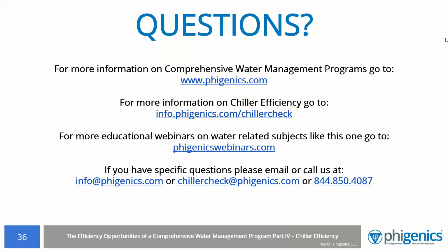Okay, great. The next question is around chiller surge. What are the top ways or options to eliminate chiller surge? Well, that's a good one. Surge occurs for a couple of reasons. One is a heavy load surge, where your condenser pressure is higher than the lift capability of the compressor, probably due to fouled tubes or air in the machine or low condenser water flow or high condenser water temperature. Your head pressure is getting too high, your evaporator pressure is getting too low, so that you have a reverse flow of gas through the compressor.